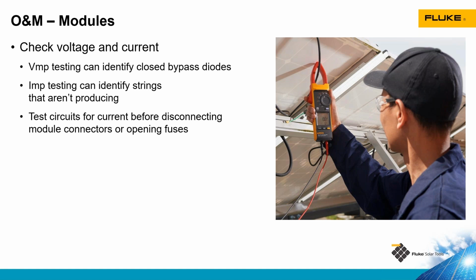With our modules, we can also test voltage and current. So we can do maximum power and open circuit voltage testing, looking for reduced voltage in that case. We can do current testing to see how strings are comparing to other strings. Most frequently with current testing in solar, we're looking for the absence of current. So I've shut my system down. I need to open up a fuse holder or a connection between modules which are not load break rated. So I want to verify there's no current in that circuit before I open up those pieces of equipment.